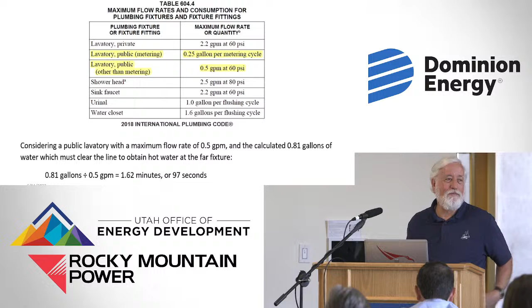That's the maximum flow rates. So basically if we take the 0.5, the better of them, 0.81 gallons divided by 0.5 gallons per minute, it's 1.62 minutes, or 97 seconds. So if it's metered with the waving, double that number. Is anybody going to stand there for 3 minutes waving their hands trying to get hot water? No. And even if they're full use, everybody's in there all the time, you're never going to get any hot water.